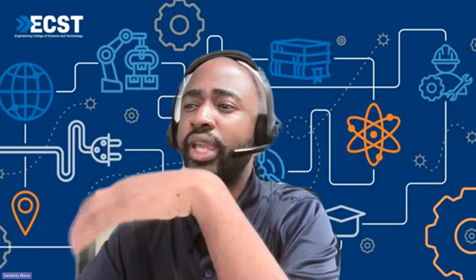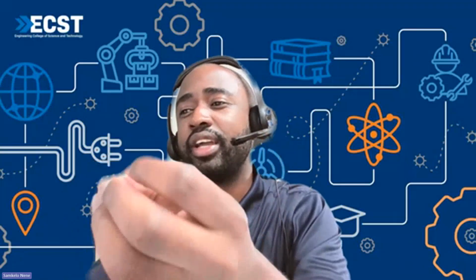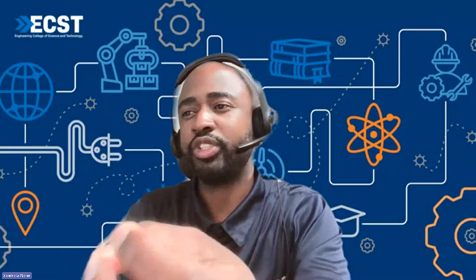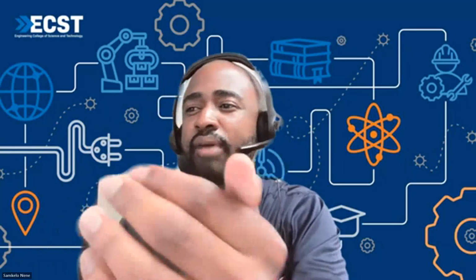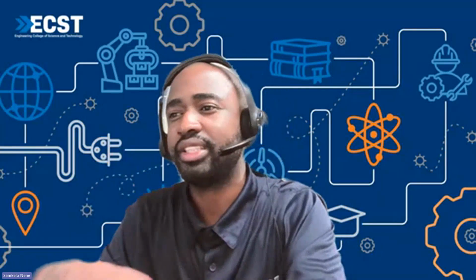Whereas with the fast frequency response, the primary is within seconds, and the fast frequency response is in milliseconds. With that one, we employ inverter-based resources like batteries and also distributed energy resources. Basically this one is about injecting power if there is more demand than the supply, or if there is less demand and more supply, we absorb that power. So it becomes that game of matching the generation with the demand.